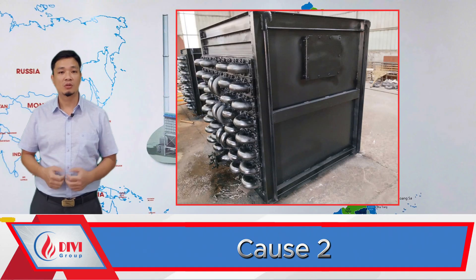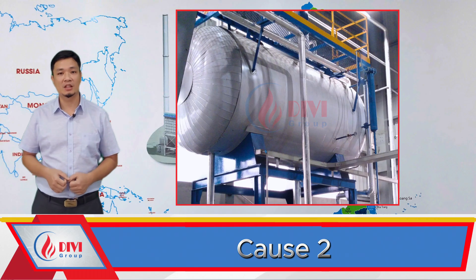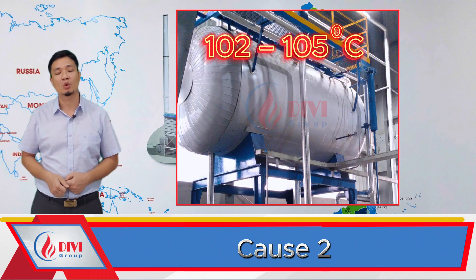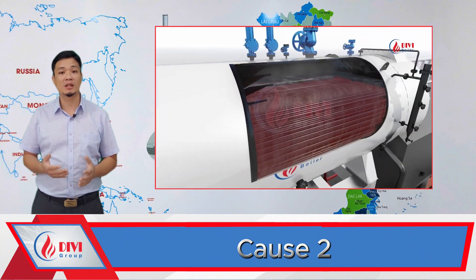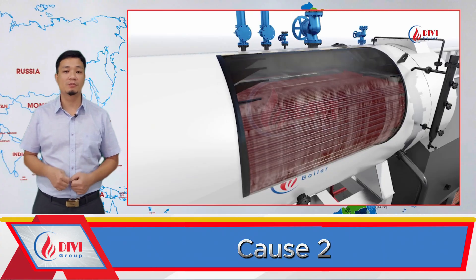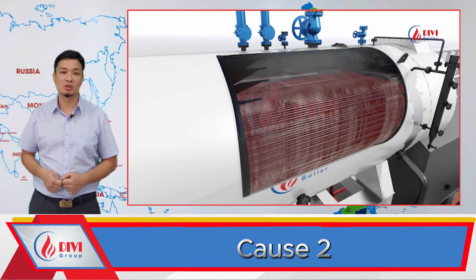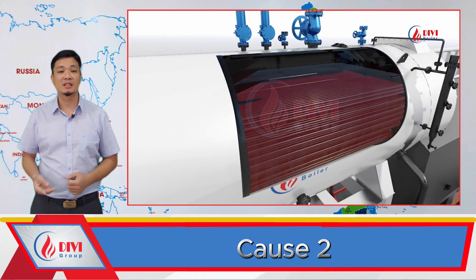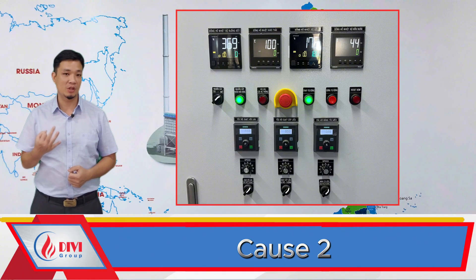Cause two: feed water too cold. Normally, the system uses a deaerator tank to preheat the feed water to 102–105°C before it enters the economizer. If the deaerator isn't properly heated, cold water enters the boiler. Even with the economizer, this water may not be heated enough. When cold water hits hot steam-generating zones, it reduces the overall temperature quickly, dropping steam pressure. In this case, check the deaerator tank temperature and make sure its steam heating system is functioning properly.